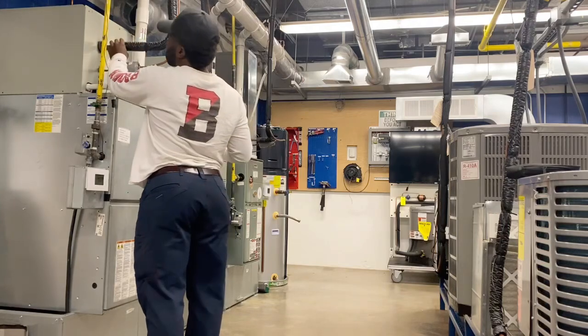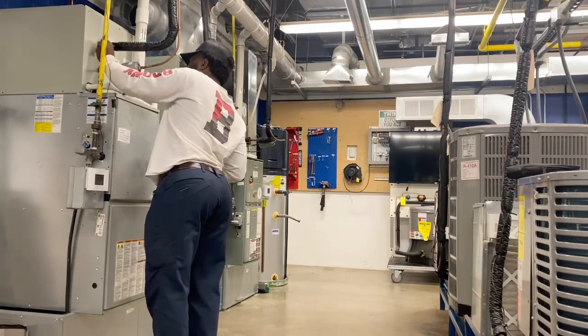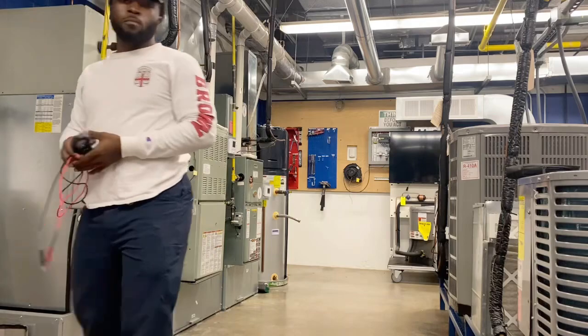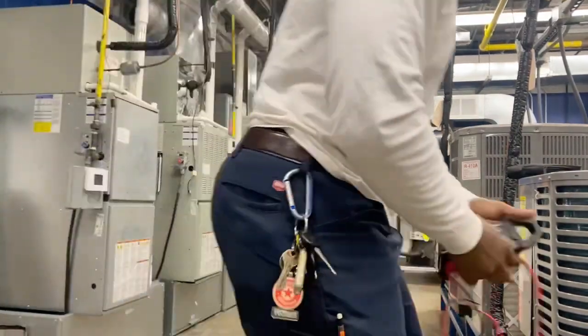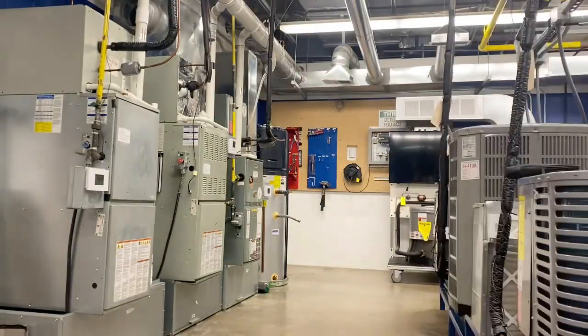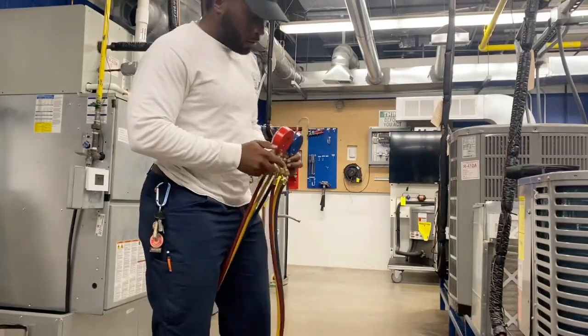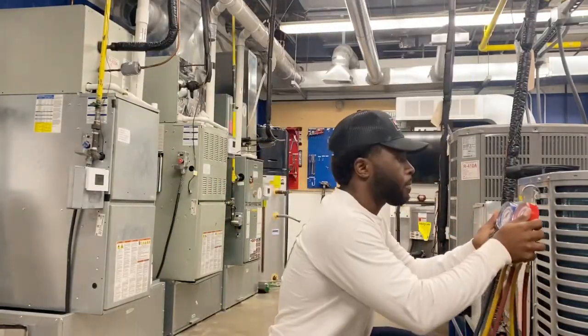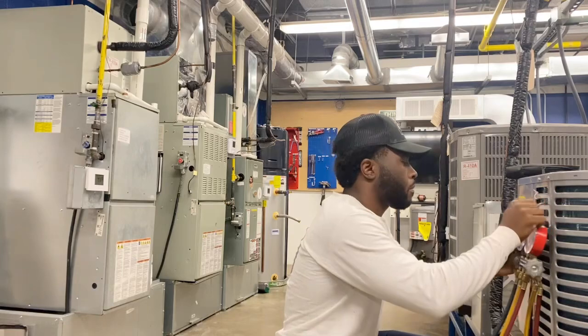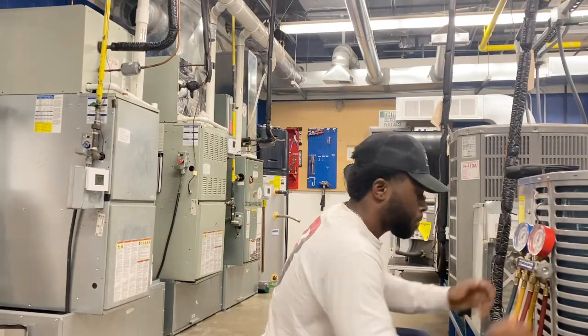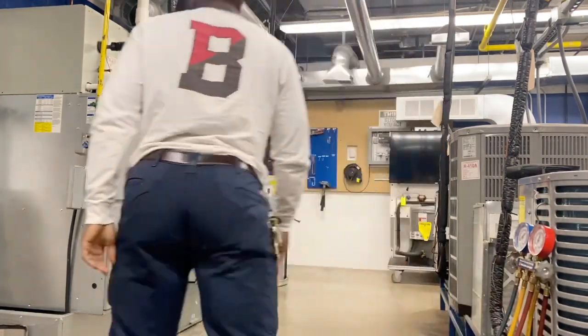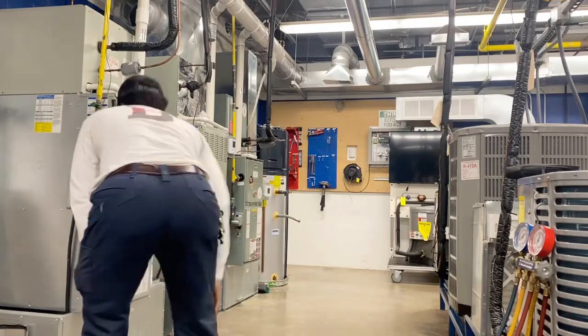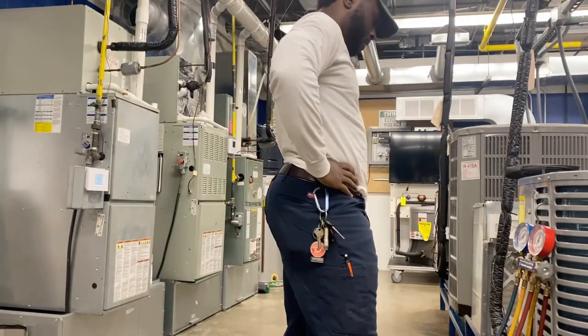So what I'm working with is a piston distributor. It's not a TXV, it's a piston. So what that means is I'm going to be more focused on superheat than subcooling. To figure that out, I've got to hook up and get temperatures of the lines and figure it out from there.